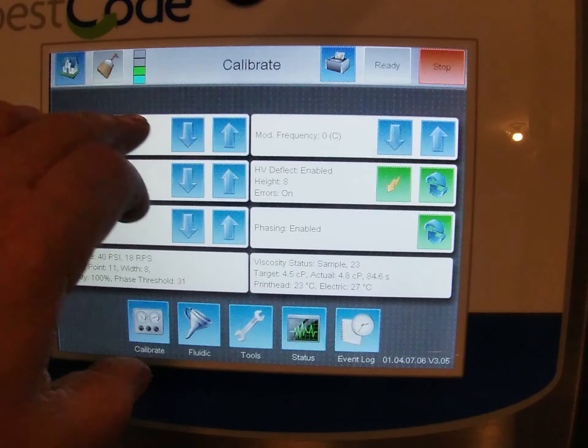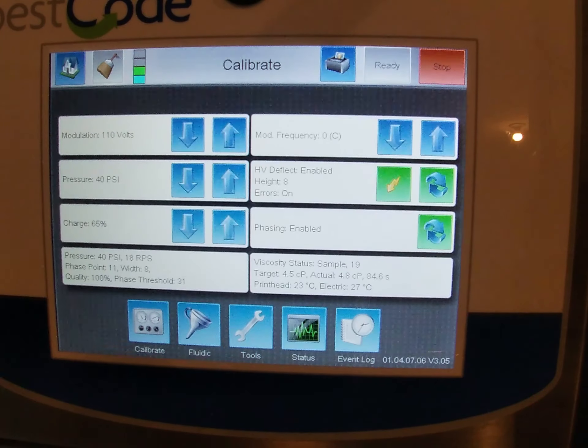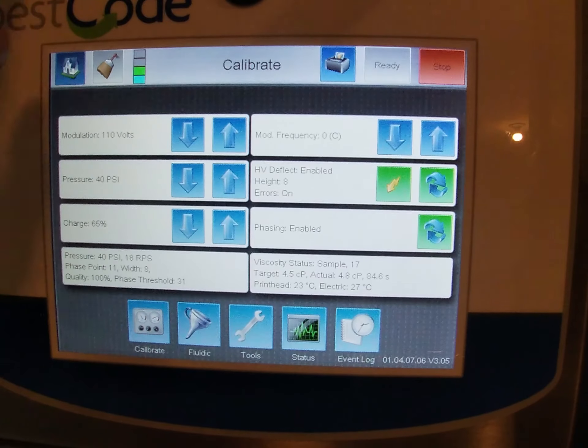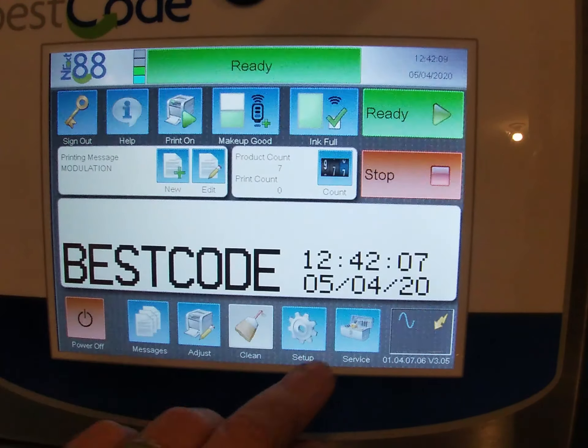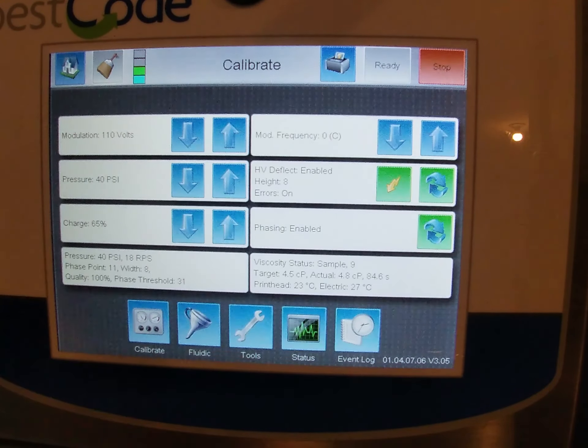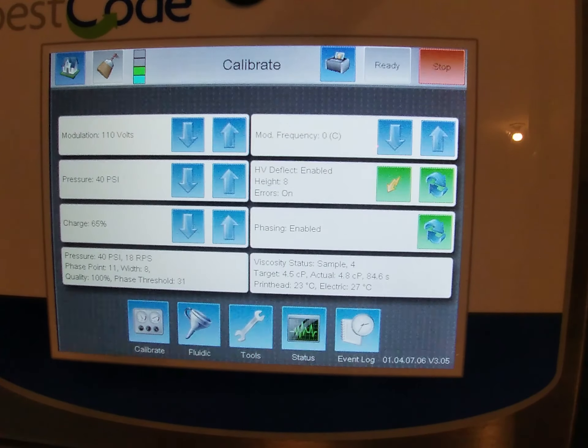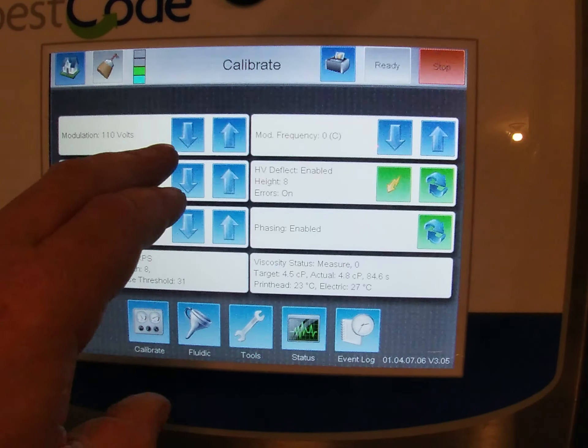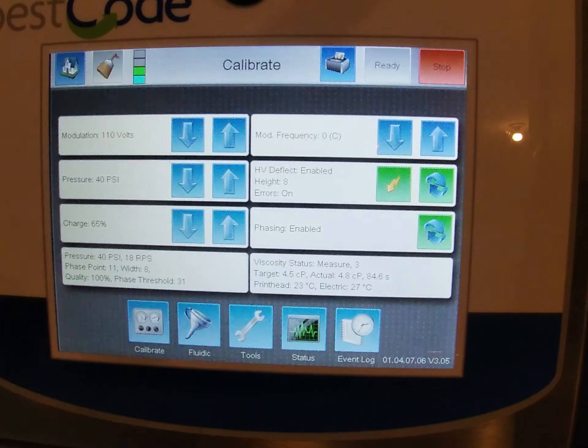So the modulation setting is right here. Modulation is currently set to 110 volts. And this is in the service screen. So from the home screen, we're going to go into service. And you see the modulation is up the top left, the same screen with the viscosity reading. So what I'm going to do is first of all, I'm going to change this voltage. I'm going to take it down to the minimum.